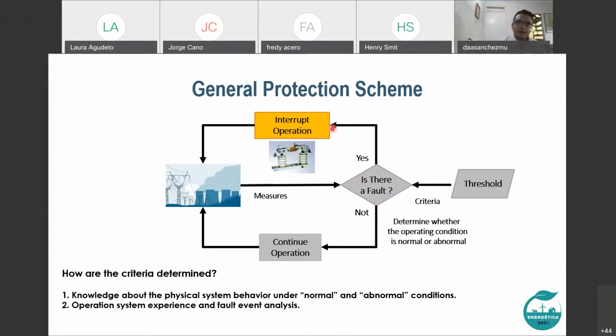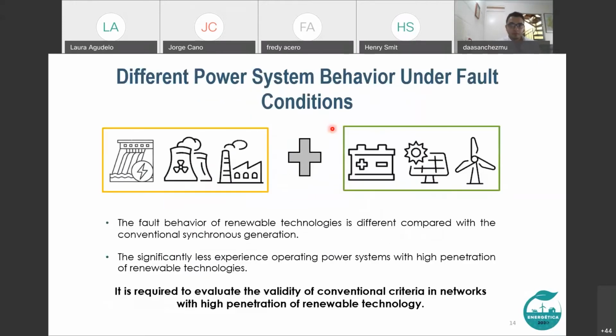Now, these thresholds are the most important part in a system protection. So, how are the criteria determined? Well, first, it is required to know the physical behavior of the system under normal and abnormal conditions. Second, according to experience in operation and failure event analysis.